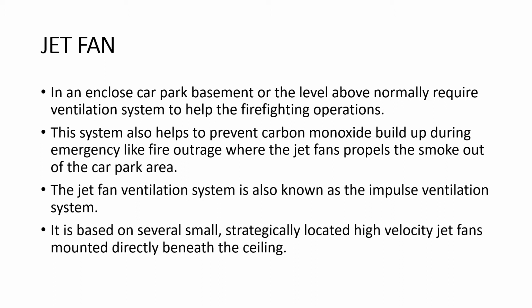So we move on to jet fan. An enclosed car park basement or the level above normally requires a ventilation system to help the firefighting operations. This system also helps to prevent carbon monoxide build-up during emergencies like fire outbreaks, where the jet fans propel the smoke out of the car park area. The jet fan ventilation system is also known as the impulse ventilation system. It is based on several small, strategically located high-velocity jet fans mounted directly beneath the ceiling.